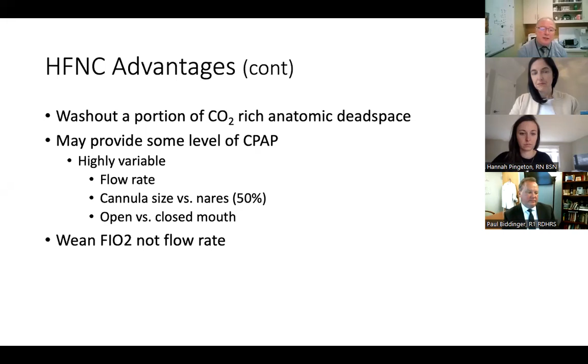The CPAP that these generate is related to the flow rate that we use, the cannula size versus the nares, and whether the patient's mouth is open or closed. Now, the cannula size should be about 50% of the size of the nares, but we have 2 cannulas and we have an infinite number of patient sizes. So it's hard to make that exactly 50%, but we want it to be open. We don't want it to be fully closed like a CPAP system because we don't want inadvertently high pressures to develop. And then once again, once the flow rate is determined, you should wean the FiO2 as the patient gets better, not the flow rate.